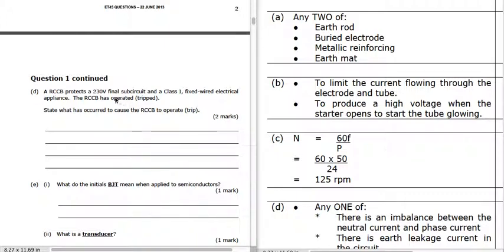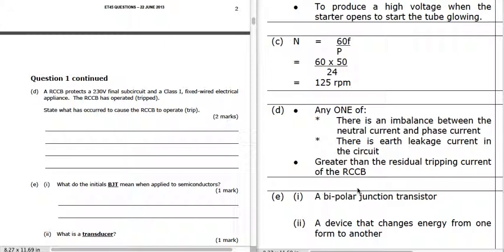We've got an RCCB protecting the 230-volt final sub-circuit, class 1. The RCCB is tripped because there's been an imbalance between the two currents — between the phase and the neutral current. There's been an earth leakage in the circuit, so some of that current has leaked out, causing an imbalance in the phase and neutral. That leakage is greater than the residual tripping current of the RCCB. Dependent on the sensitivity of the RCCB will depend how much current it takes to make that out of balance.